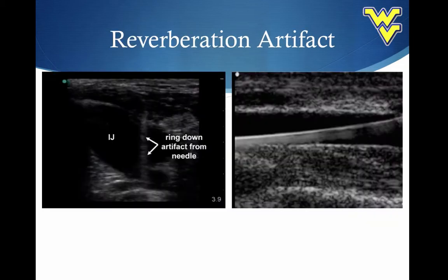Another important artifact, probably the last one I think, is reverberation artifact. You'll often see this when we see another very intense ultrasound reflector. It's kind of the opposite of a shadow because you get this bright white reverberation artifact that goes down. So in this case we have a needle here, and what's happening is the ultrasound beam gets bounced back and forth multiple times across here at different time periods, and so the machine interprets that as something all the way down at a farther distance all the way across the screen. That's what it shows here. And here we see this wire in a vessel that's been cannulated, and we see all these reverberation artifacts down from the wire. A common artifact, and again sometimes it is a helpful artifact that helps us identify structures or like foreign bodies in tissue.